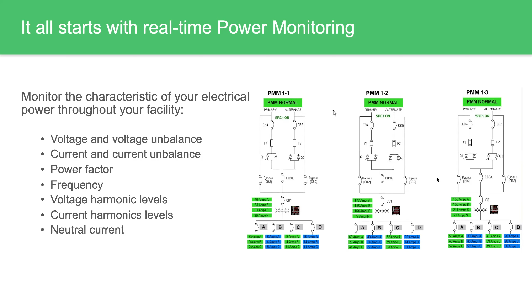So where does it all begin? Power management is based on having real-time system-level visibility of electrical parameters throughout your facility - not just basic measurements like voltage, current, and frequency, but also attributes that give insights into power quality, such as power factor and harmonic distortions, plus more advanced electrical parameters. It's also important for detecting things like current leakage, ground current loops, and excessive harmonics, especially in large and critical facilities. They use power meters to monitor all these parameters in real time to operate and maintain a safe, reliable system.